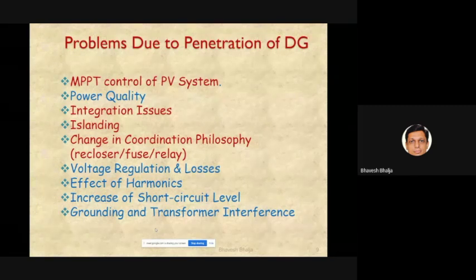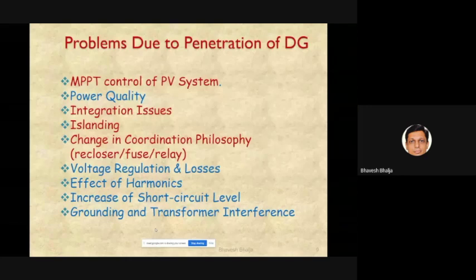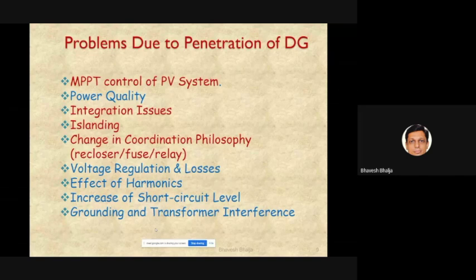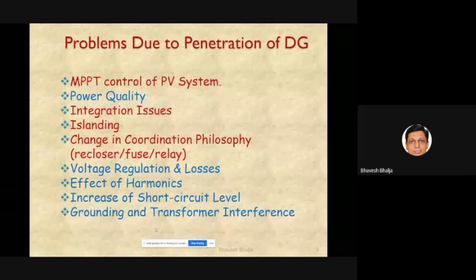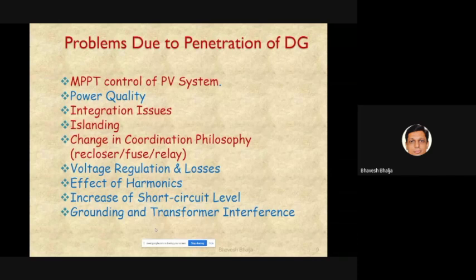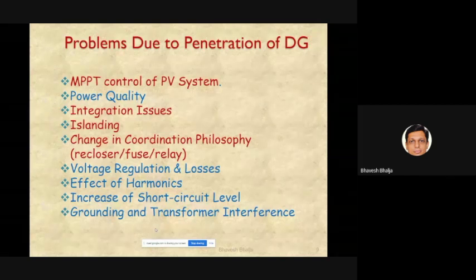Voltage regulation and losses are also important: when DGs like solar and wind are incorporated, voltage regulation changes and losses change as well. Harmonics impact was already covered under power quality. Another critical issue is increase of short-circuit level — when no DGs are present, switchgear (circuit breakers, isolators) is selected based on utility capacity alone.